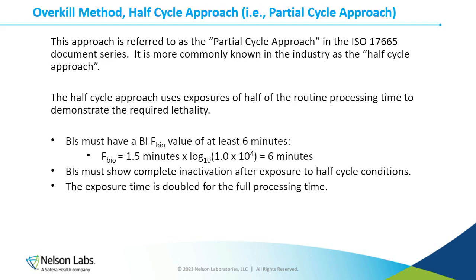The first validation approach available in the ISO standard is the partial cycle approach, commonly referred to as the half-cycle approach. This approach uses half of the routine processing time to demonstrate the required lethality. BIs must have an Fbio value of at least six minutes. That allows us, through complete inactivation of that BI, to demonstrate a six-log reduction of a microorganism with a D-value of 1.0 minutes. Once demonstrated in the half-cycle time, the exposure time is doubled for the full processing time.